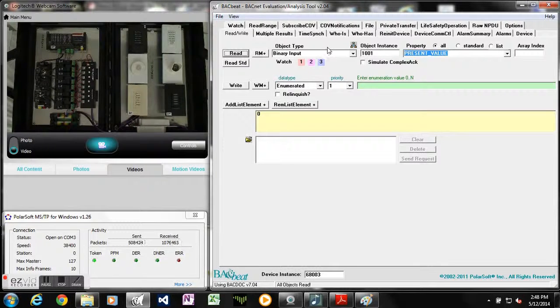So if we wanted to test the next station, button 1, this would be binary input number 9, because we have 8 allocated binary inputs for the first switch, and then the very next one would be binary input number 9. So we can read this one. It's at a 1, I push it again, it's at a 0.